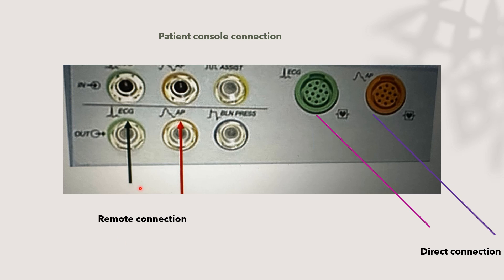There are two types of patient console connection: direct connection, where the cable is connected directly from the patient's pressure line or ECG to the console; or remote connection, using the bedside monitor or anesthesia monitor. Direct connection is preferred, because remote connection introduces some delay — possibly seconds — which can affect the cardiac cycle.